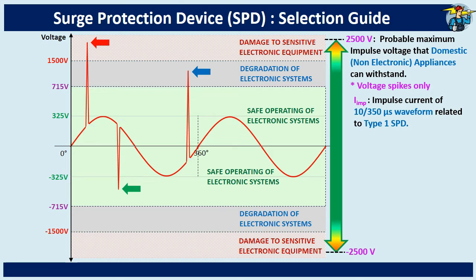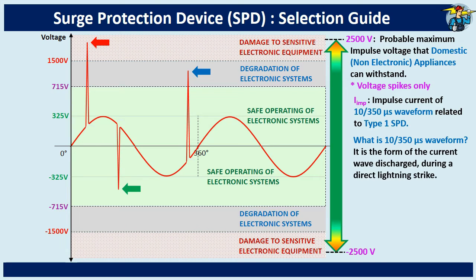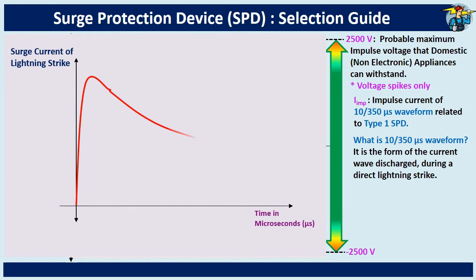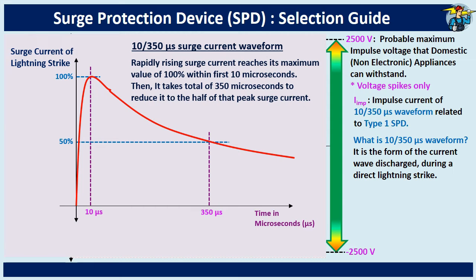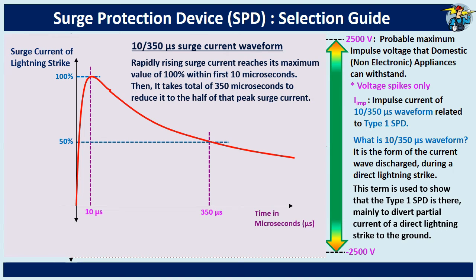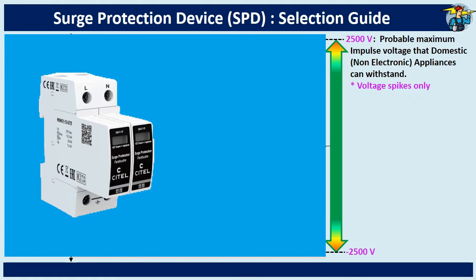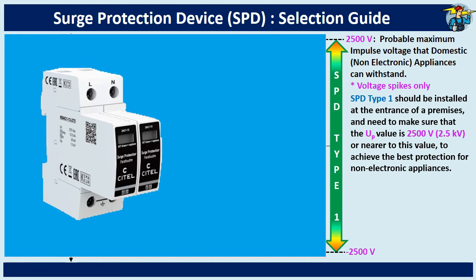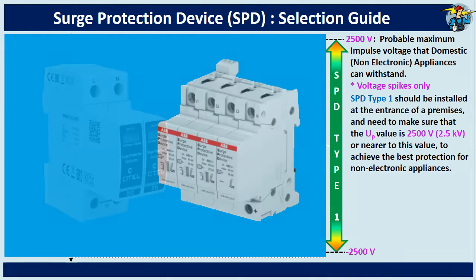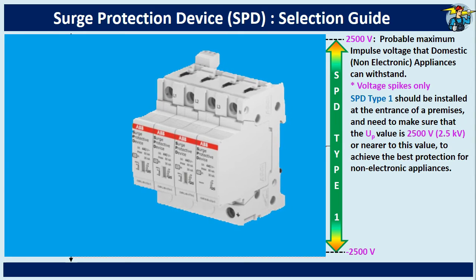Iimp marked on a type 1 SPD is the impulse current of a 10/350 microsecond waveform. It is the shape of the discharged current wave during a direct lightning strike. Rapidly rising surge current reaches its maximum value of 100% within the first 10 microseconds. Then it takes a total of 350 microseconds — a fairly long tail — to lower it to half of that peak surge current. This term is used to show that the type 1 SPD is there mainly to divert partial current of a direct lightning strike to the ground. SPD type 1 should be installed at the entrance of a premises, and its UP value should be 2500 volts or closer to this value, to achieve the best protection for non-electronic appliances.